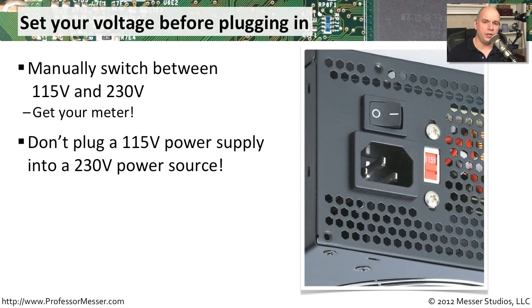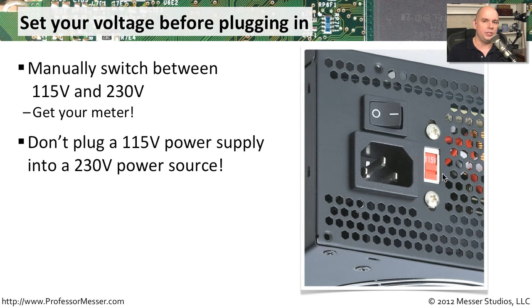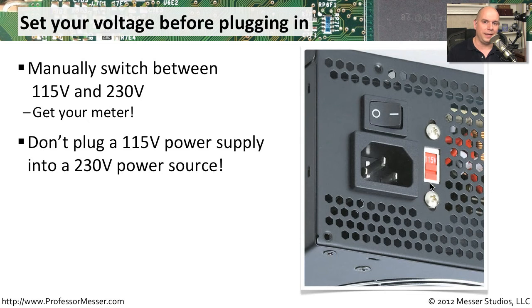Some power supplies have a physical switch on the back that switches between 115 volts and 230 volts. If you're going from one country to another, make sure that switch is set correctly. If you aren't certain of the voltage coming out of the wall, grab your multimeter, connect it to the wall socket, and see what voltage it registers. If there's a 230 volt source and you've configured the supply for 115 volts, it will overload and destroy that power supply very quickly.